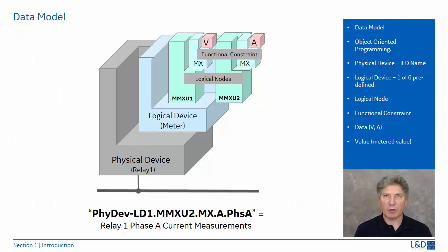If you have an understanding of the data model of IEC 61850, you should recognize the format of object-oriented programming. Let's take a quick review of this. The physical device is also known as the IED name. The logical device defines the data group type, which we'll discuss in detail next. The logical nodes define the type of information that will be received. The functional constraint groups the logical node into categories. For example, ST for status, DC for description, MX for measurement. The data breaks down the category further, such as volts, amps, breaker position. And the last part is the value. In this case, phase A magnitude.